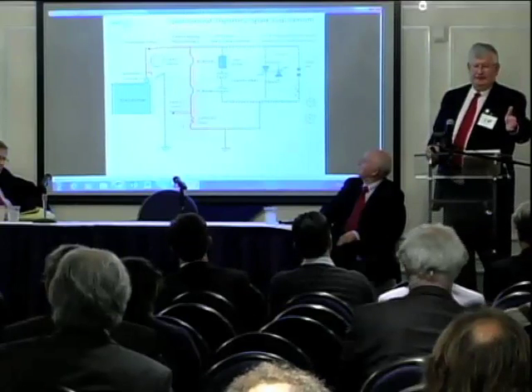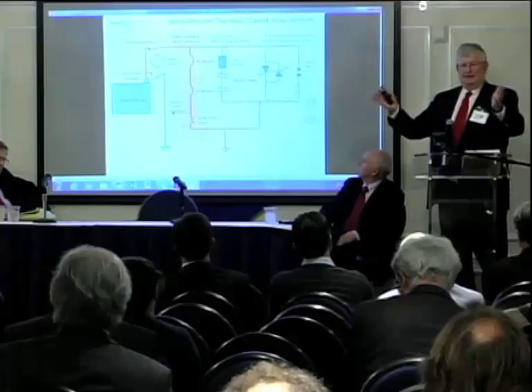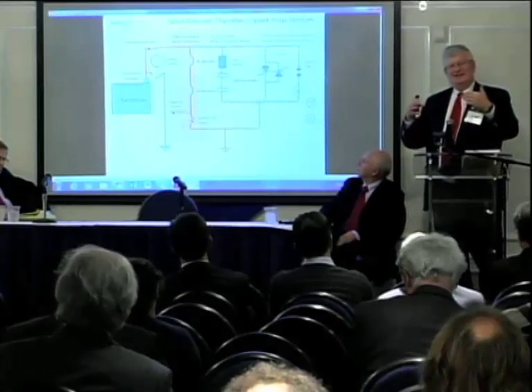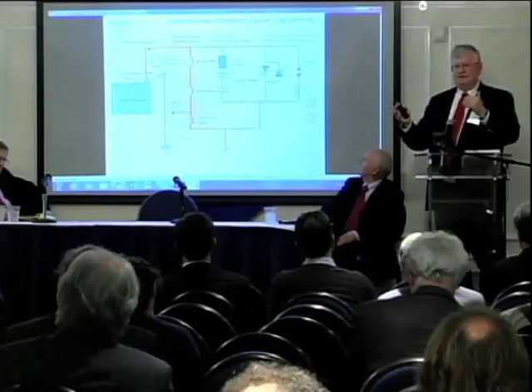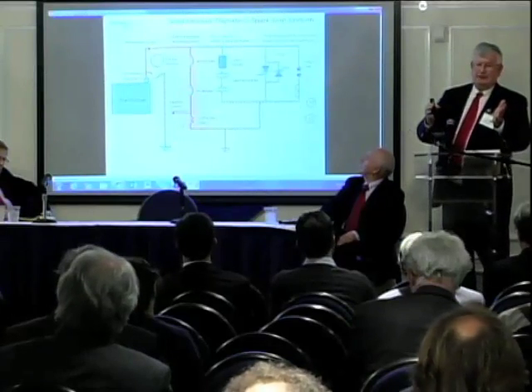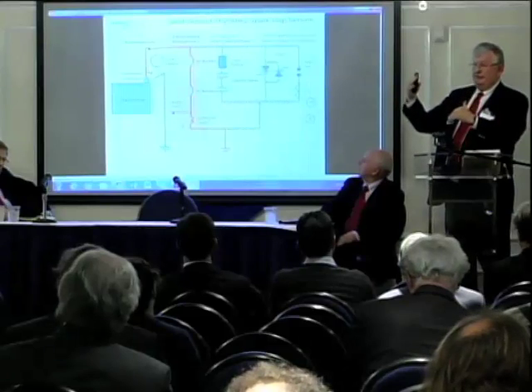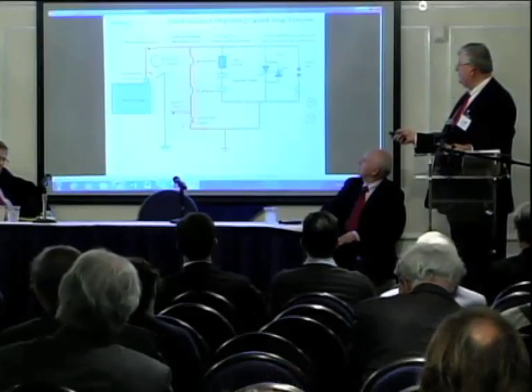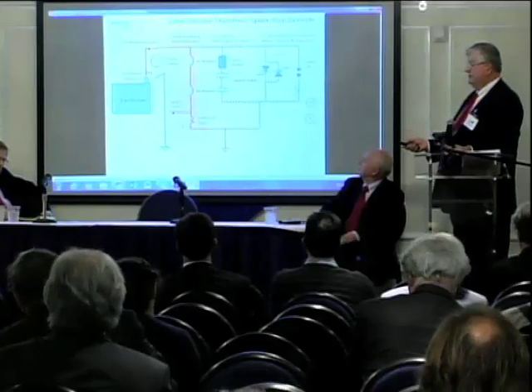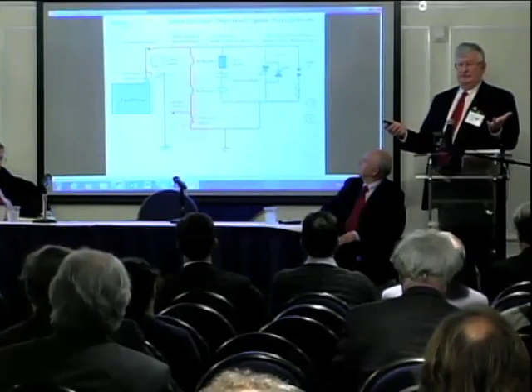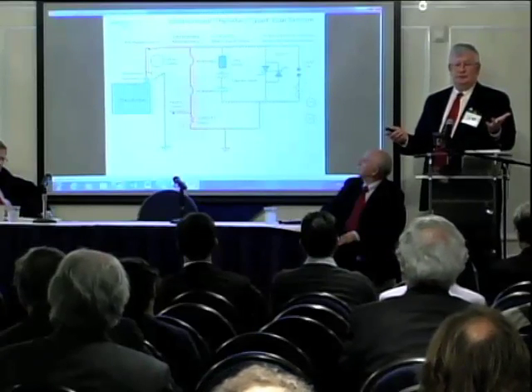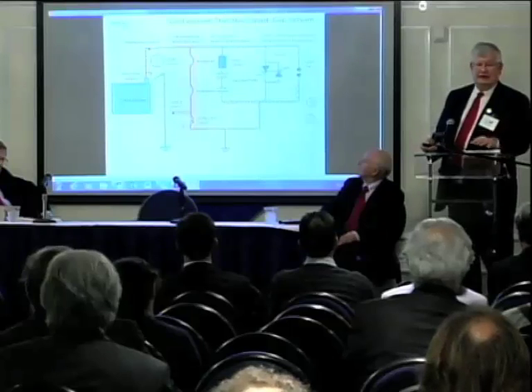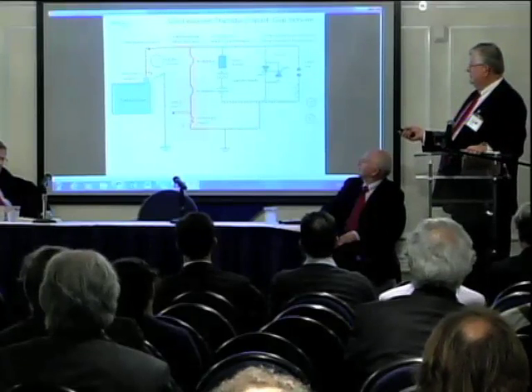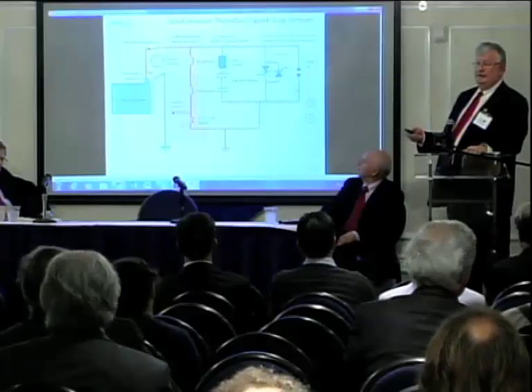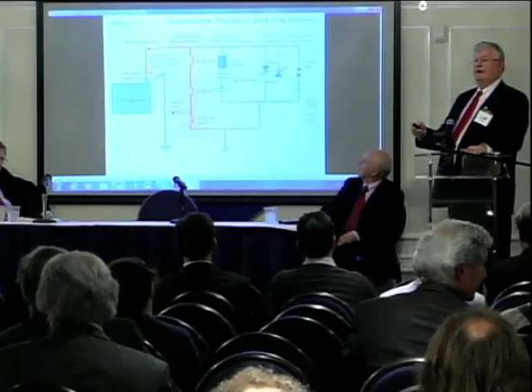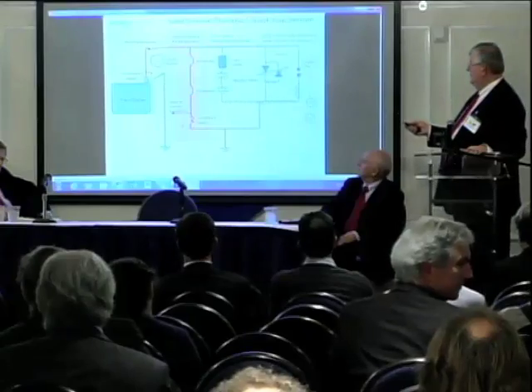150 times 20 volts is 3,000 volts. So for long lines in other states, maybe even at 30 volts per kilometer, we decided to make a beefier unit. We did that with two capacitor banks, and now it's 8,000 volts, so 8 kV, which we think will handle virtually any situation. If there's an extra long line for EMP at 50 volts per kilometer, we can add more capacitor banks and it'll still operate.